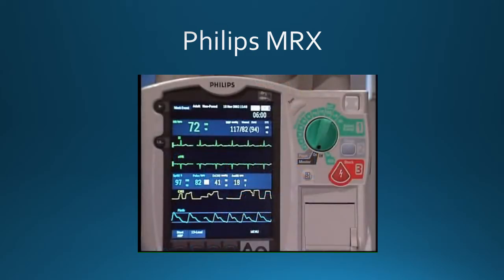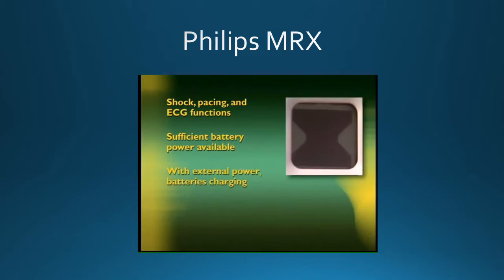To assess operational performance and alert you if a problem exists, the MRX routinely performs automatic self-tests. The results of the tests are reported through the Ready for Use indicator and messages when you turn the device on. The blinking black hourglass symbol indicates the shock, pacing, and ECG functions of the device are ready for use, and sufficient battery power is available for device operation. Additionally, a blinking black hourglass, together with the presence of external power, AC or DC, indicates that installed batteries are being charged.